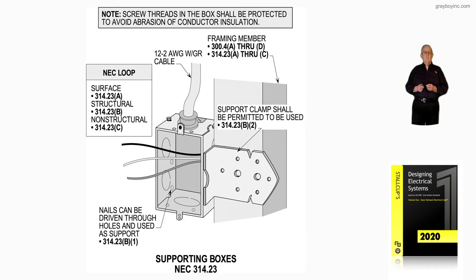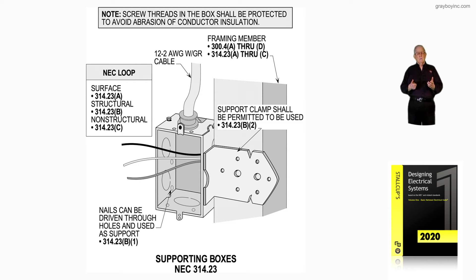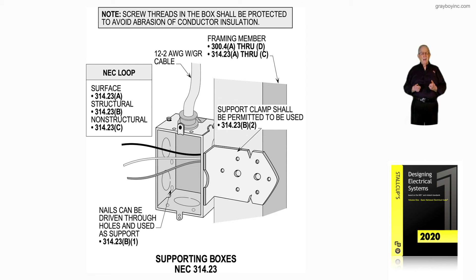Notice we have 12-2 with ground cable coming into that box, and all we're showing here is mainly the support means of the box. If we want to learn about the surface of the box, it would sit back and you could put a half-inch sheet rock, the finishing material of the wall, over it. 314.23(A) covers the surface portion, and 314.23(B) covers the structure portion, while non-structural means would be 314.23(C).